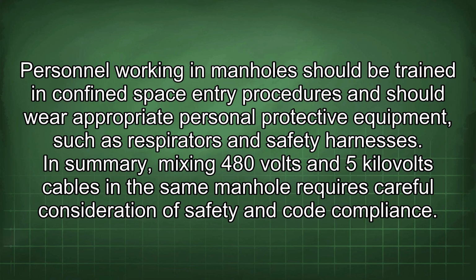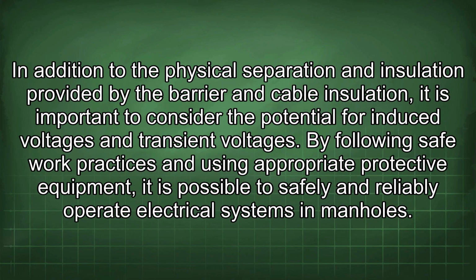In summary, mixing 480 volts and 5 kilovolts cables in the same manhole requires careful consideration of safety and code compliance. In addition to the physical separation and insulation provided by the barrier and cable insulation, it is important to consider the potential for induced voltages and transient voltages. By following safe work practices and using appropriate protective equipment, it is possible to safely and reliably operate electrical systems in manholes.